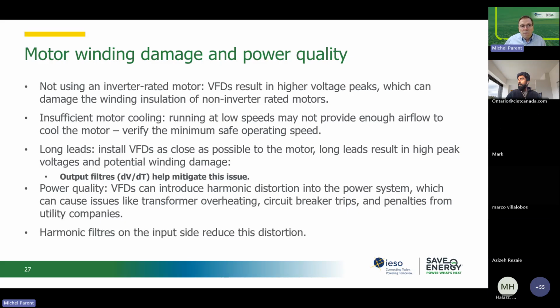You want your VFDs as close as possible to the motor. The further you are from the motor, the higher those peaks will be. So even an inverter duty motor can burn out if your drive is installed way far and you've got this long lead and you don't have an output filter. Sometimes you'll hear the term dV/dt filter.